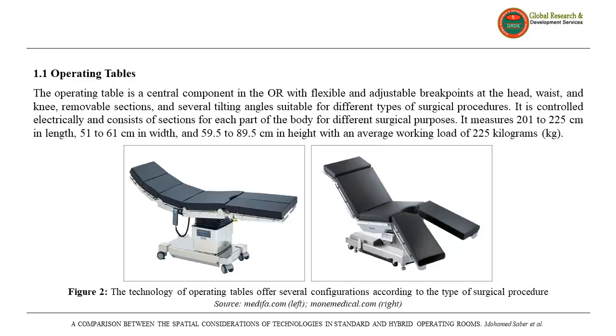From the major components of the standard operating rooms, the operating table. It's positioned at the center of the room and controlled electrically, and consists of a number of movable sections and breakpoints to adapt to the different surgical purposes. It measures between 201 and 225 cm in length, 51 and 61 cm in width, and 59.5 and 89.5 cm in height, with a wide range of tilting angles.